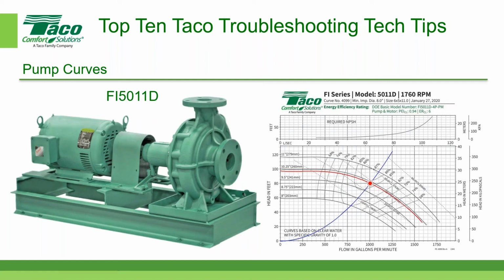Now, if you recall, they said that they didn't actually measure the flow. What they did was they took the pressure differential across the pump, and they said that that pressure differential was 92 feet. So if I go over here, I'm going to draw a line here.